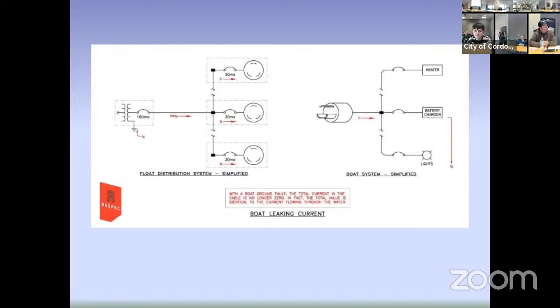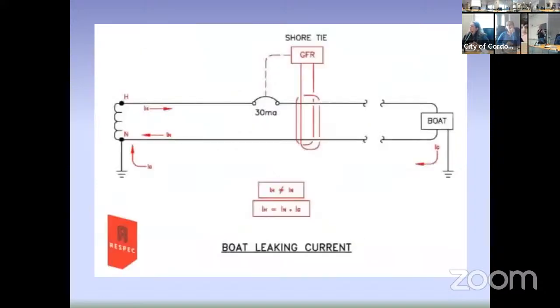That's kind of hard to read. And this is really just talking about the same thing. When this happens, the summation of the hot lead and the negative lead is no longer zero, and it will trip the circuit breaker. Let's hit the next one. So this is just saying the same thing. You can see the illustration. If that current is coming through the water up into the transformer, it's bypassing the neutral and tripping.